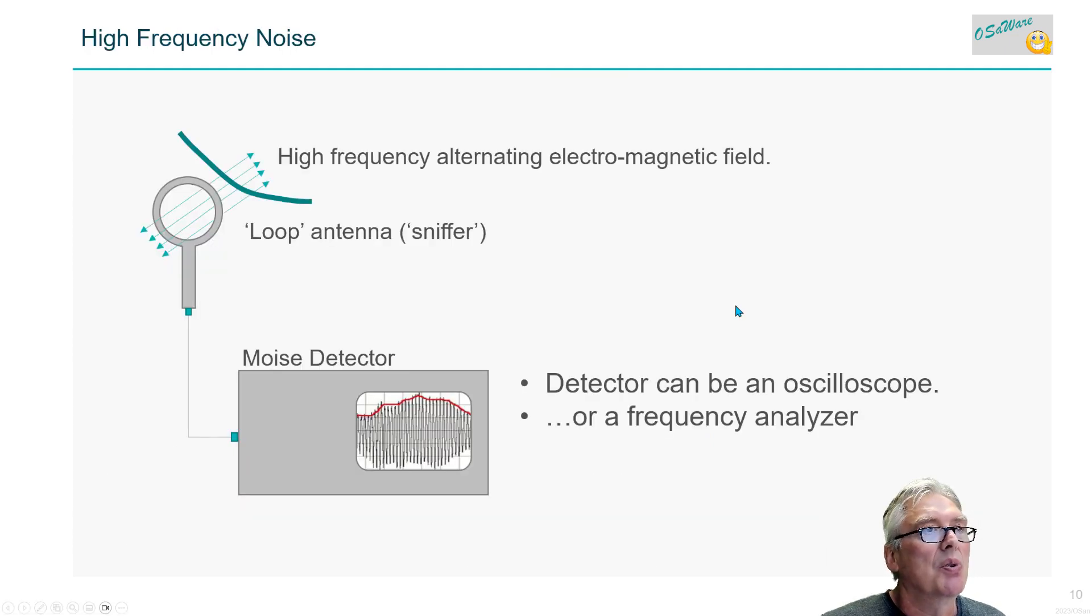Then there's high frequency noise. How to locate electromagnetic noise? We can use an antenna and detect this electromagnetic noise. Maybe here's a shield or broken shield - you can see high frequency oscillating through the shield or cable. Use a loop antenna and then have a noise detector - for instance, a spectrum analyzer. Here is an amplitude for a frequency - high frequency noise that might be causing the problem. You can use a frequency analyzer or oscilloscope to detect this.